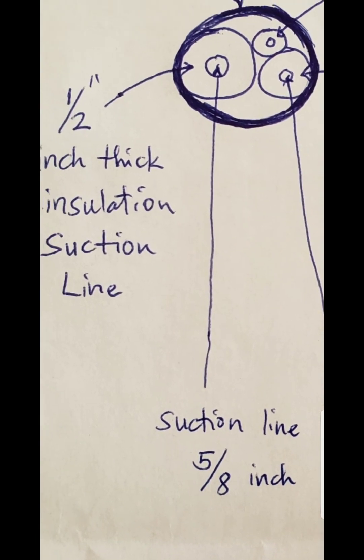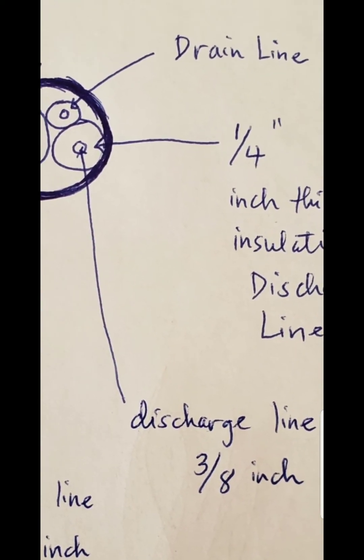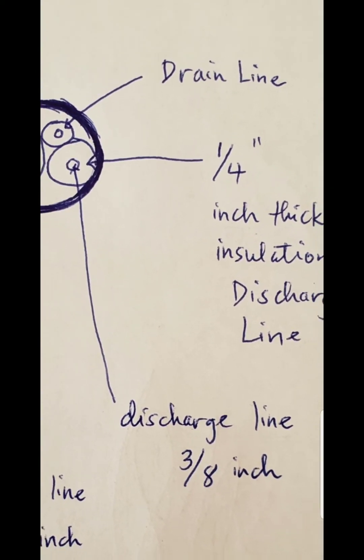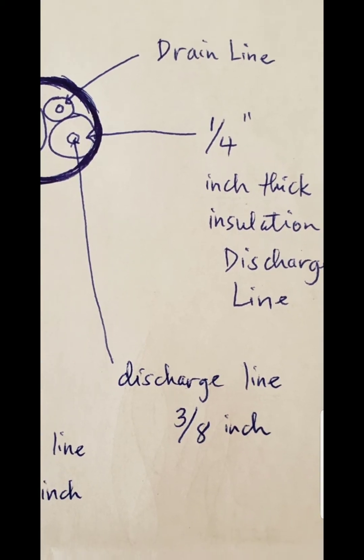And the insulation of the suction line is half inch. Now take note that the insulation is round, so the overall thickness is twice, twice one-half inch, and I will show you that in the solution. For the discharge line, it's a quarter inch thick insulation and the discharge line itself is 3/8 inch.